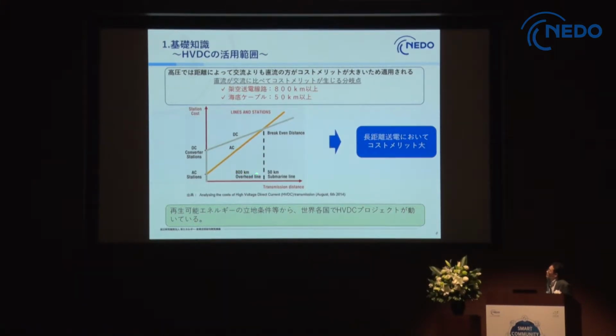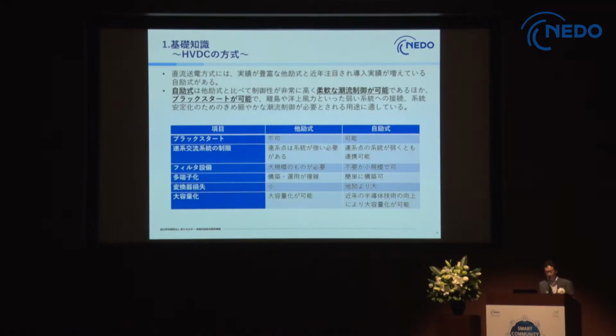For example, in the case of overhead transmission lines, if the distance is longer than 800 km, or more than 50 km in the case of submarine transmission lines, DC is considered cost competitive compared to AC. So in the area of HVDC, if PV, wind power, and renewable energies are used more in the future, there will be higher needs for longer distance transmission. One of the reasons for the focus on HVDC comes from that situation as well.